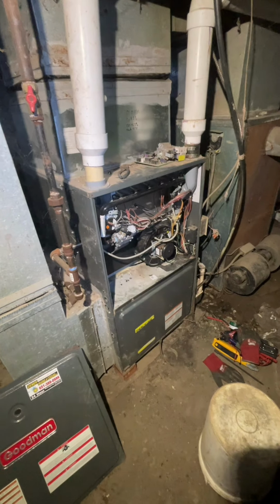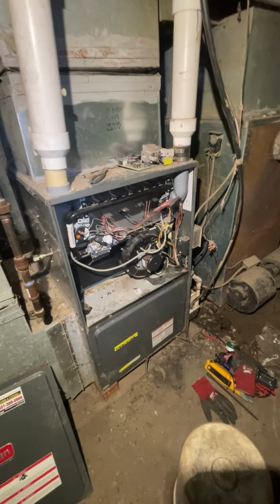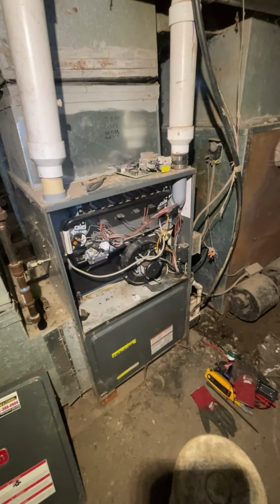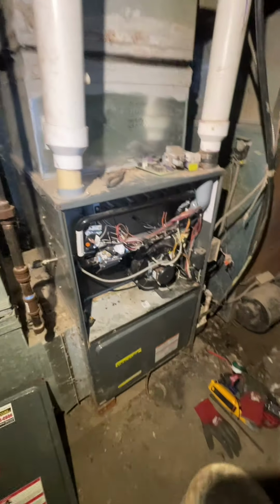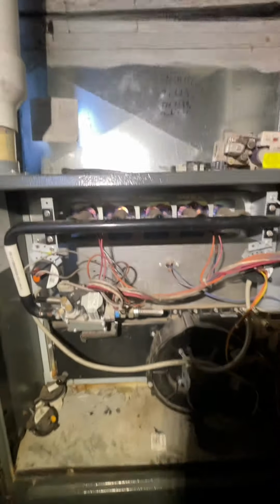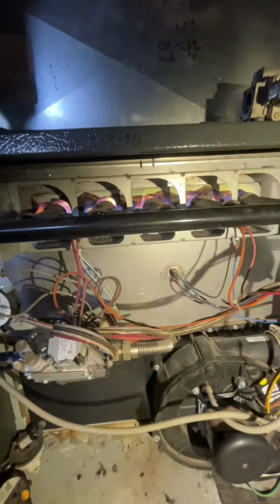Today we're working on a Goodman furnace. This is a big one too, probably about 100,000 BTU. I'm going to shut the light off so you can see the flame. You see how that flame is real yellow? This unit has a bad heat exchanger, and I'd guess the heat exchanger is probably plugged up.